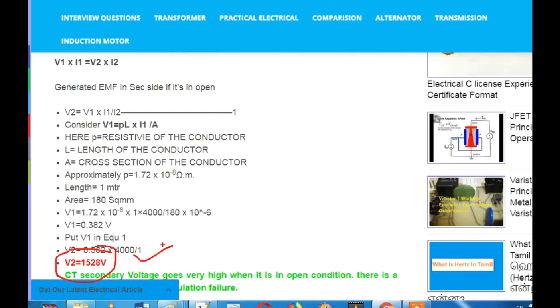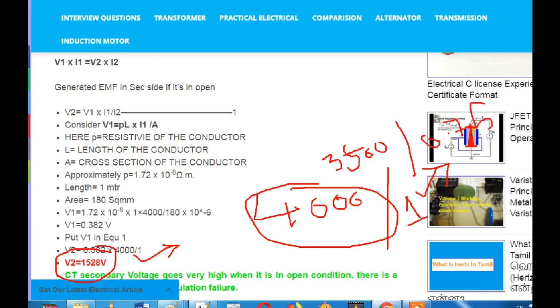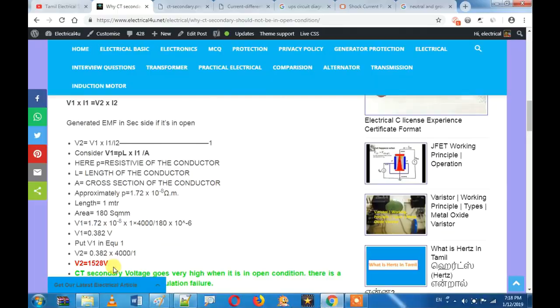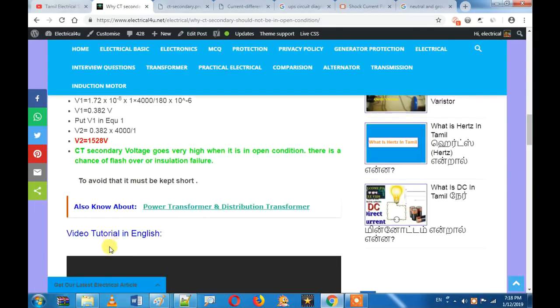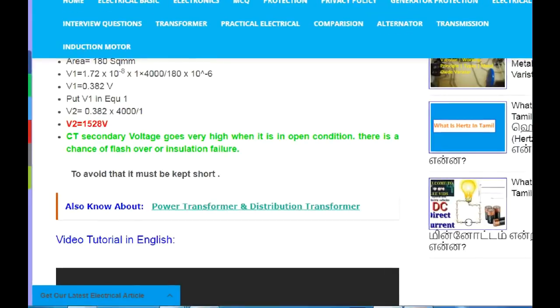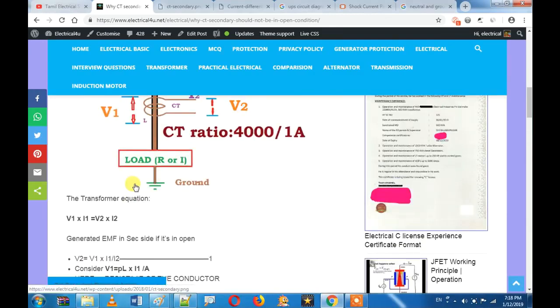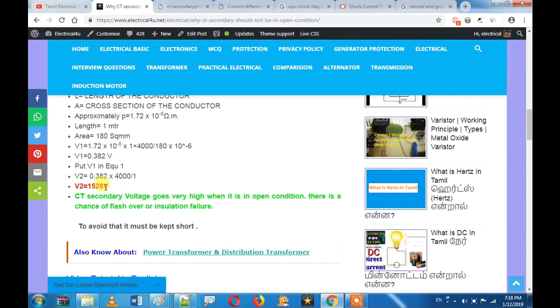It depends on the current flow. For example, I1 and I2 at 4000/1 amps — the maximum CT current is around 3500 amps, giving 0.75 amps on the secondary. That is the secondary voltage behavior. The CT secondary voltage builds up automatically if the circuit is open.